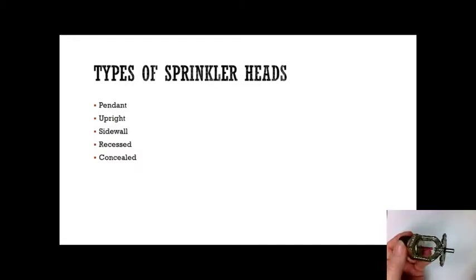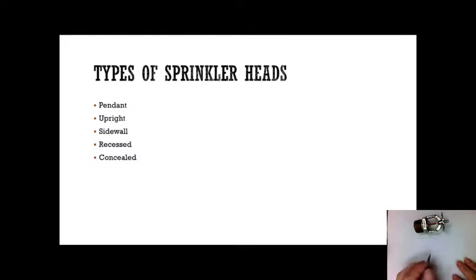There are different types you see. Sometimes this particular one might end up being in a wall. It may be recessed. So here's our ceiling, we have our ceiling part going here, and it's recessed up. That means the ceiling is raised, and here is the gadget itself, the sprinkler head with the flange. So what happens then, water, with the flange usually level with this, will disperse out. Do you see the water spurting out and going in different directions?